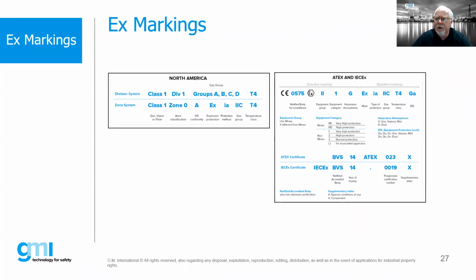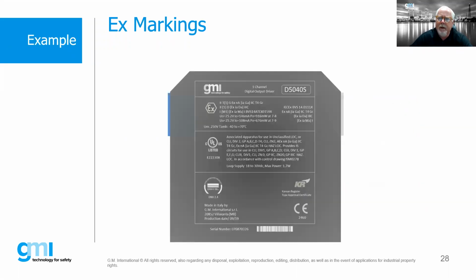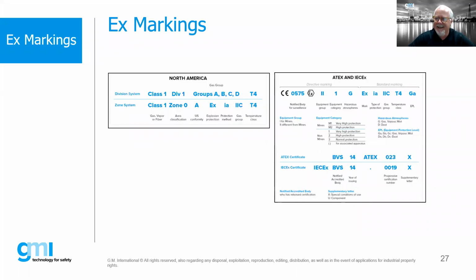Now, the EX markings, I'm going to skip this one right now because we're going to use an example of an EX marking in just a second. So we'll move forward from this slide and go right to this one. Actually, let me go back. It probably makes sense to at least reference this to show you what we're looking at. What we find here, here, and here are the requirements under the ATEX directive: we have to have an EX in a hexagon, and a CE mark telling us it's compliant to the ATEX directive. This number applies to the notified body, which is basically the testing lab that did it.